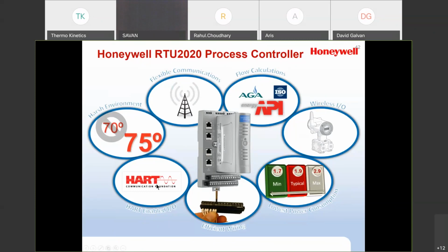It also has HART embedded in every AI and AO channel. So the one prepackaged module set that you see here will give you 8 analog inputs, 2 analog outputs, 11 discretes, and then 2 pulse inputs. You can mix and match the discretes. There's DIs and DOs. Okay, it is a full-blown flow computer. It complies with AGA and API. It has all the flow algorithms inside for Coriolis, for turbine, viscosity, orifice, you name it. Everything is there. And then it also has wireless I/O ability.